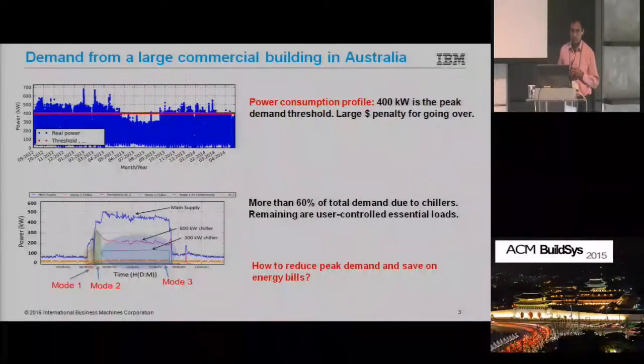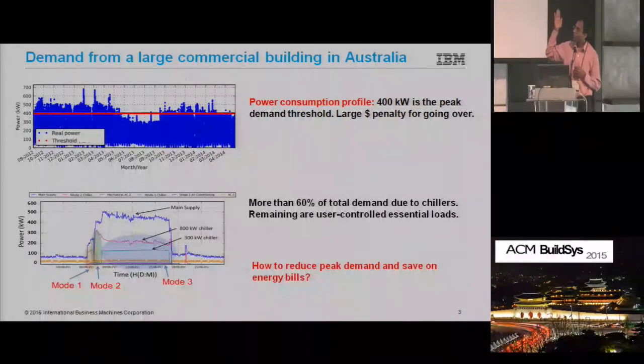Given that this is in a tropical region, you don't necessarily need heating. So the question we ask is, how can you actually reduce the peak demand to save on energy costs? The technique we propose is basically pre-cooling. The advantage is that pre-cooling the building in advance of the expected cooling time can reduce the peak, and also time shift the peak into a low energy tariff regime. That's what we'd like to exploit in the rest of the paper.